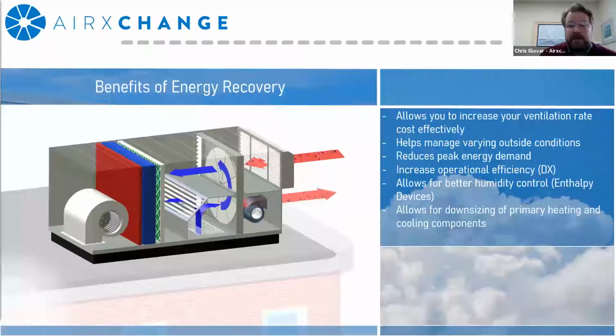It's one of the few devices in the market that allows you to reduce peak energy demand, meaning the hotter it gets, the colder it gets, the more work these devices actually do for you. If you're using it in conjunction with a DX system, most DX systems' efficiency has a tendency to drop off as you start to moisture load the coil. These devices will actually remove moisture prior to it getting to the coil, so it allows your DX system to operate more efficiently. It allows for better humidity control.